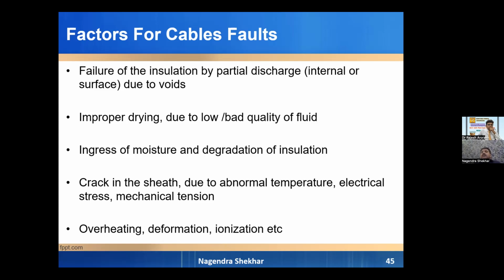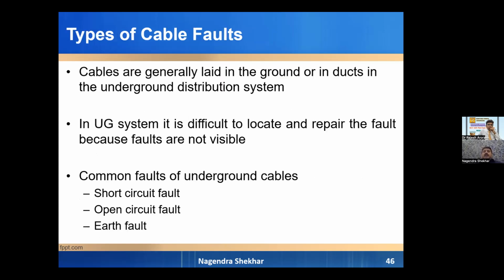If a cable is laid without a proper soft soil bed, the stones or tree roots can cause mechanical stress. Or if it is not buried at a proper depth, the roads or running vehicles can result in mechanical stress on the cable. Overheating because of overloading, deformation and ionization, etc. These are the major reasons behind cable damage and mechanical damage.